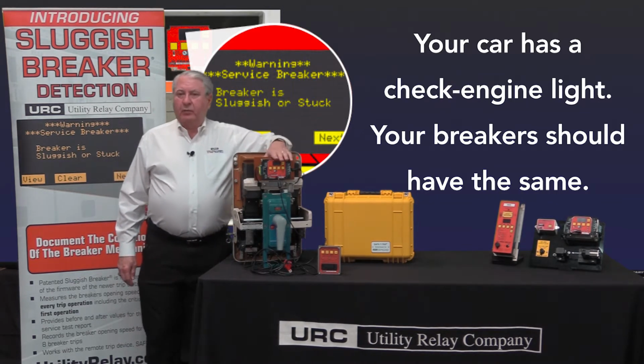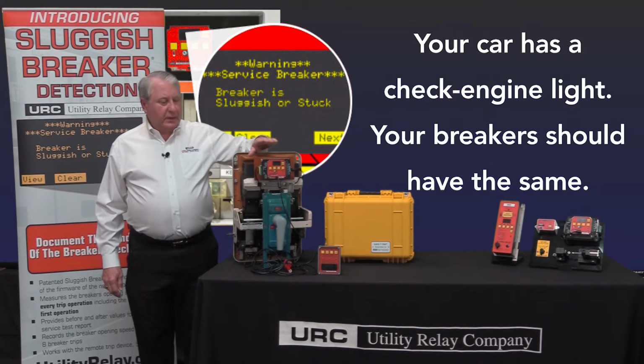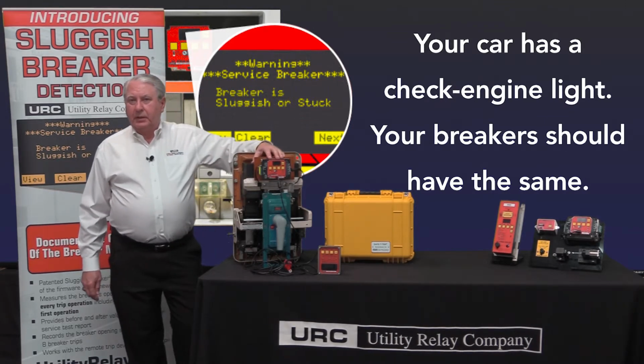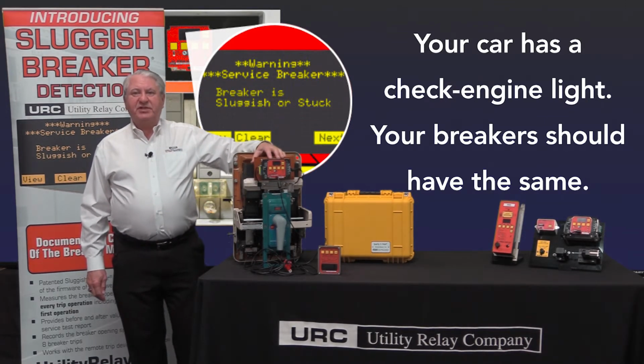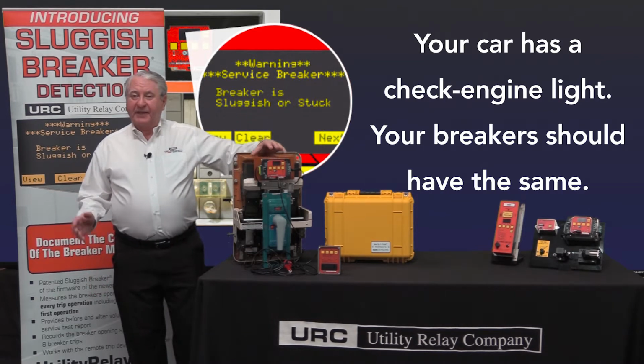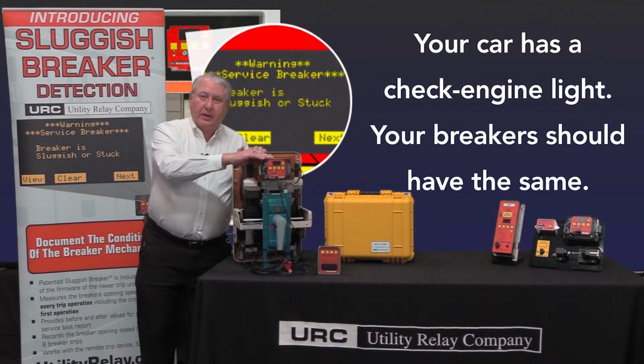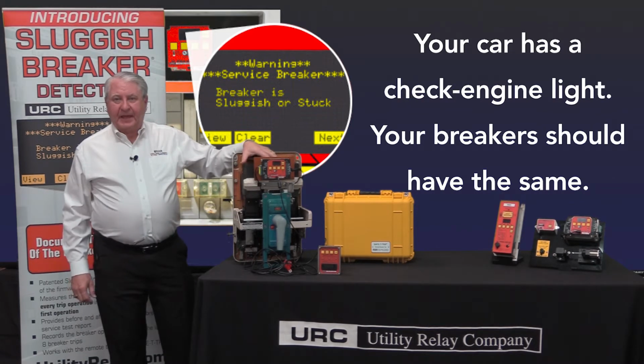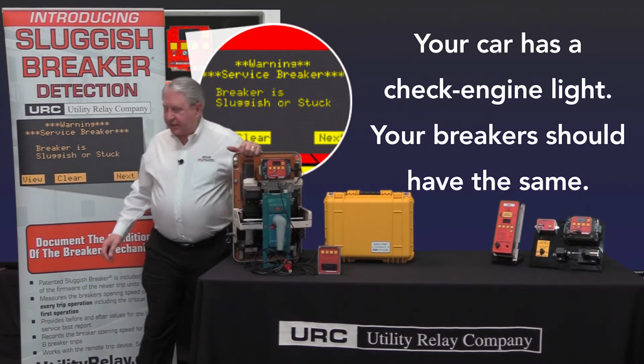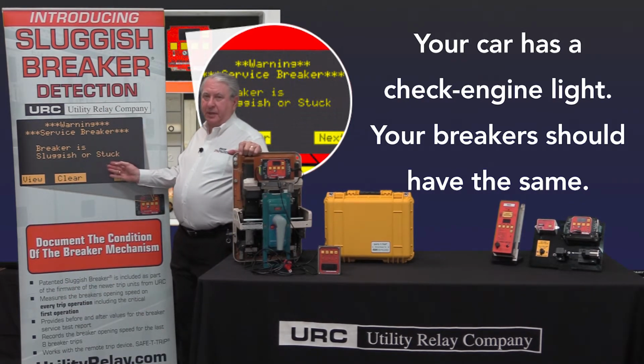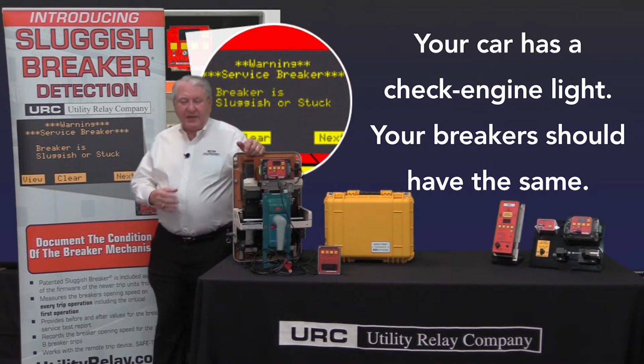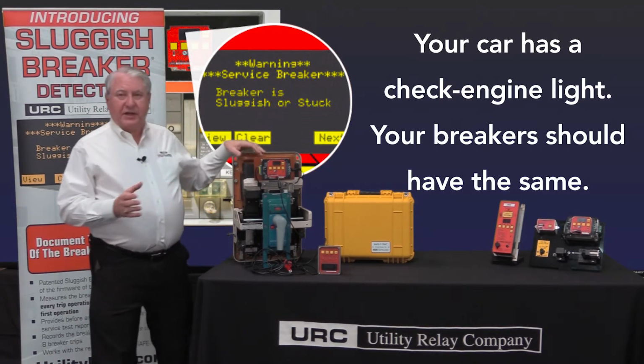So let me tell you how that works. Every time the trip unit is called on to trip a breaker, it times the opening of that breaker. And if that timing exceeds a threshold, that's one of the programming steps in the AC Pro 2, then a sluggish breaker detection message comes up telling you that you've got a problem, it's either slow or stuck, and you need some service. So let me demonstrate how that sluggish detection works.